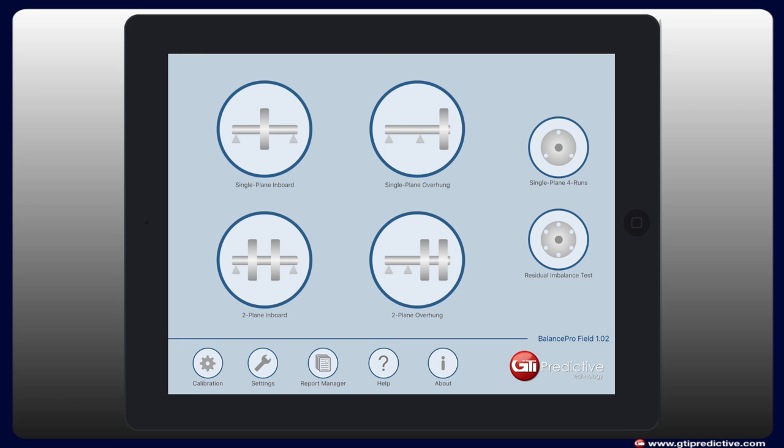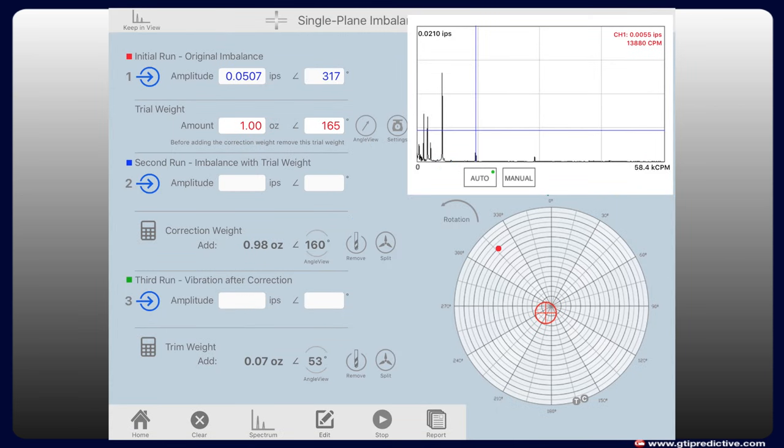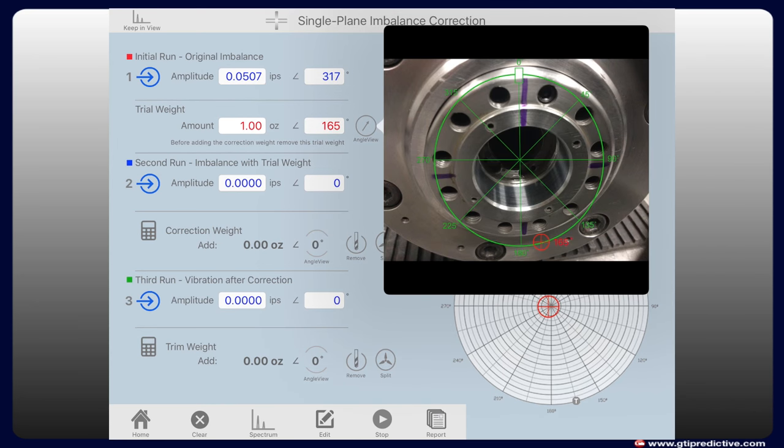To begin, select the type of balancing needed. And step one is the initial run when the technician starts the motor. By tapping the number one, Balance Pro populates amplitude and angle and tells the technician what trial weight amount to use and what angle to apply it.